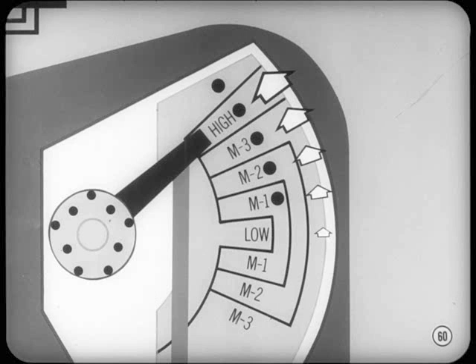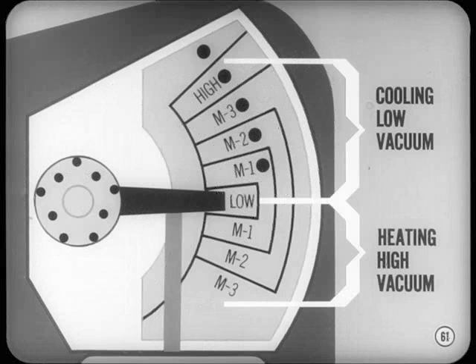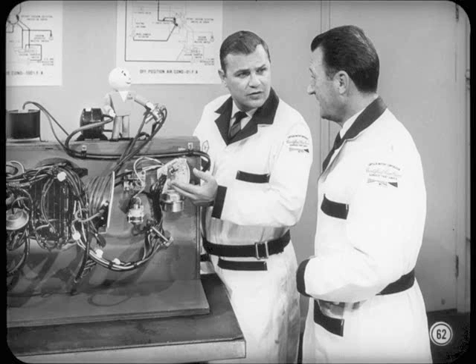5 steps? I thought there were only 4 blower speeds. There are 5 blower speeds for cooling, but only 4 speeds for heating. The highest speed is available for cooling only. The other 4 speeds are the same for heating or cooling. Highest vacuum gives high speed for heating. Lowest vacuum gives even higher speed for cooling. I've got that straight. Now maybe you could explain what has been happening over on the vacuum switch side of the power servo. Coming up, Jack.